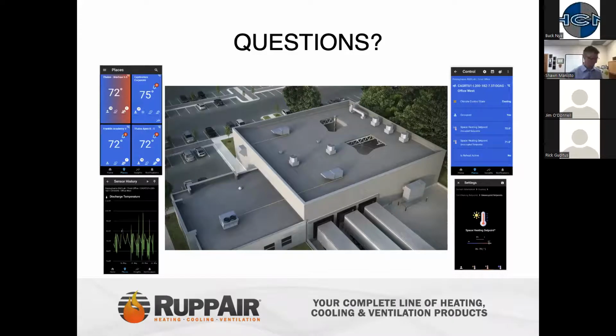Okay. So there was a question or also a statement. It might have been answered. It came up early in the presentation. It might have been covered later on, but we've experienced hot air accumulated below the ceiling of warehouses due to the supply diffusers being located at the bottom of the ductwork, and they're blowing downward with the returns at floor elevations. Is there a better way to reduce this hot air stagnation, this stratification?